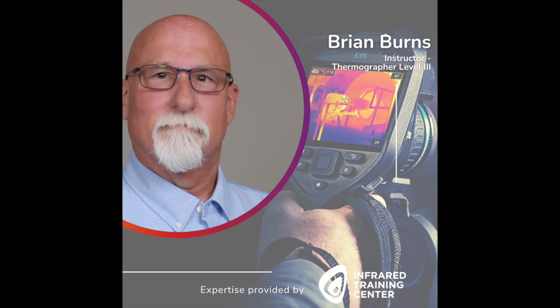Now, what you'll generally find is that we have so many positive panels and so many negative. They're sending in because it's a DC system. And where this goes into is combiner boxes. You can see a picture here of a combiner box. This may be the positive side of 96 panels that have been combined into this box before it heads down to the inverter.